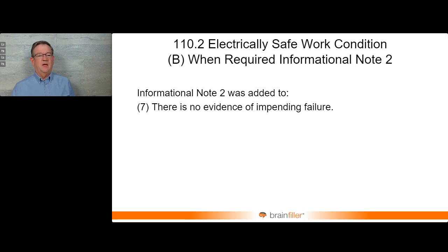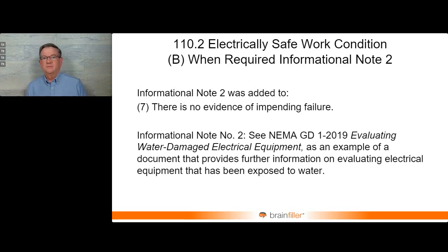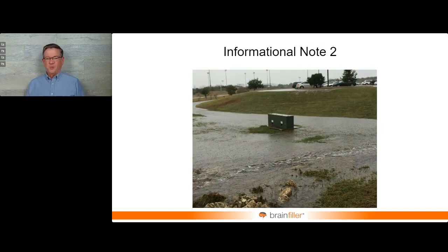But the thing about the water that I was talking about is, what if equipment has been exposed to water? Now, on NFPA 70E, there are several people from the gas and oil industry, and they're around the Gulf states, which are prone to hurricanes. And I've heard the stories over recent years about, oh yeah, our switchgear, man, it was submerged. What do you do? Well, I took this photograph too. This one really puzzled me. This was in Austin, Texas, at the Circuit of the Americas, the F1 track. I'm a big F1 fan. And this was from several years ago. A hurricane had just rolled through a couple days before. And I'm looking at that and it's like, who would have located electrical equipment in the middle of a drainage ditch? But anyway, that's what they have.